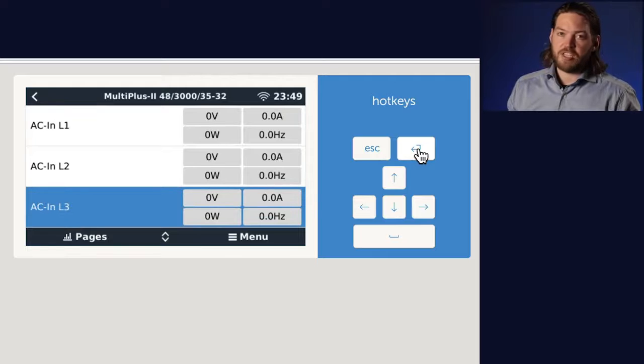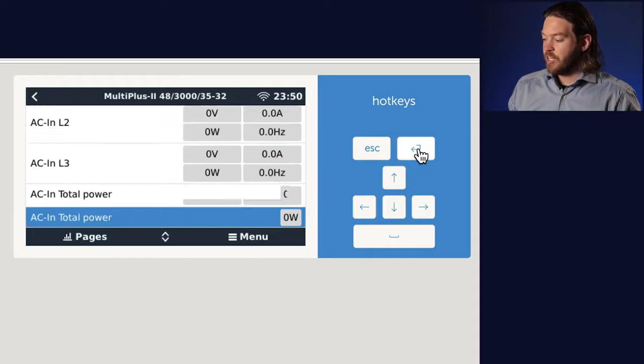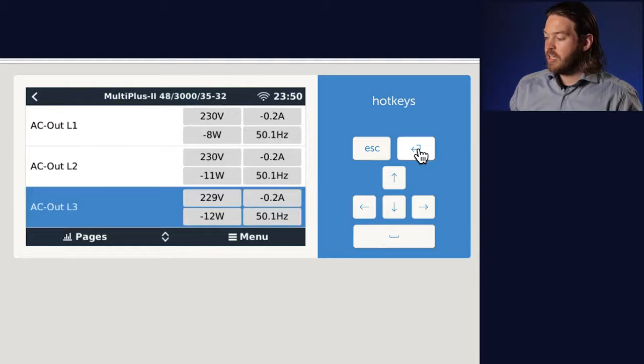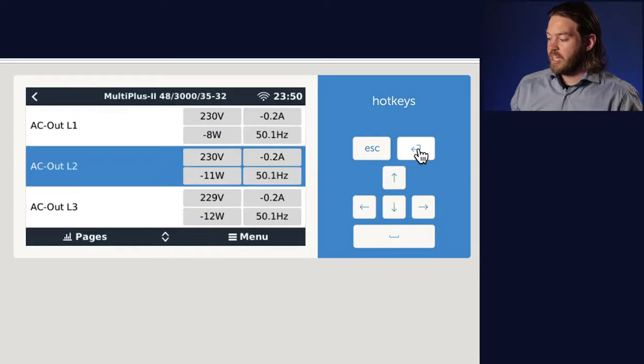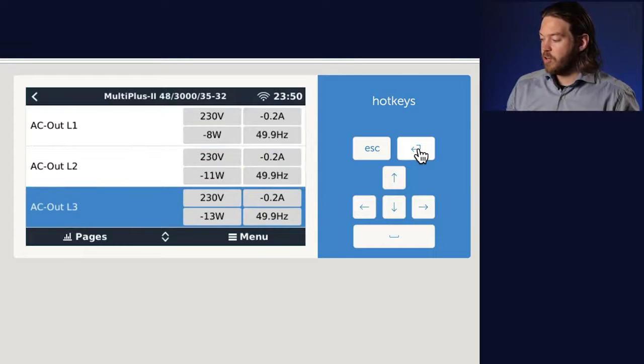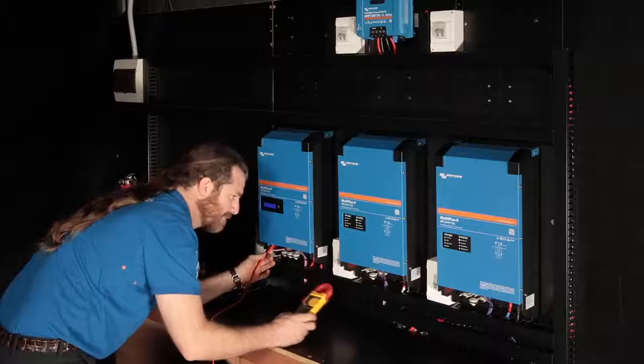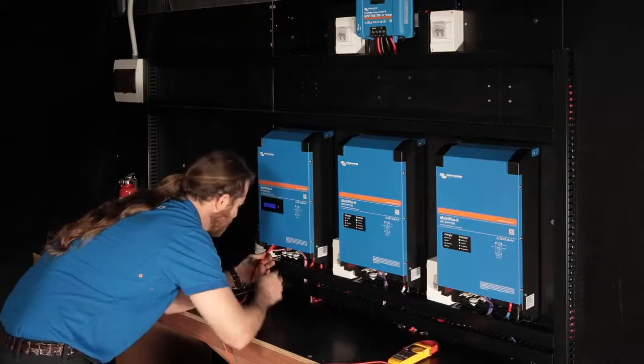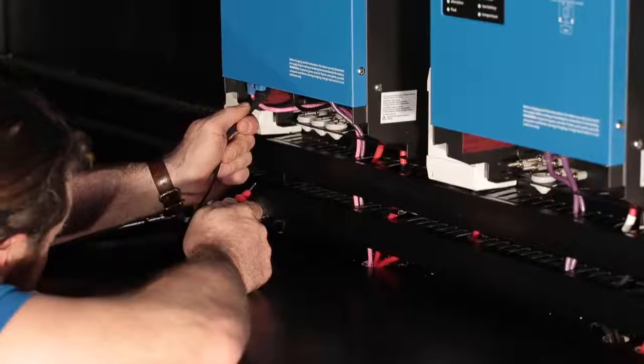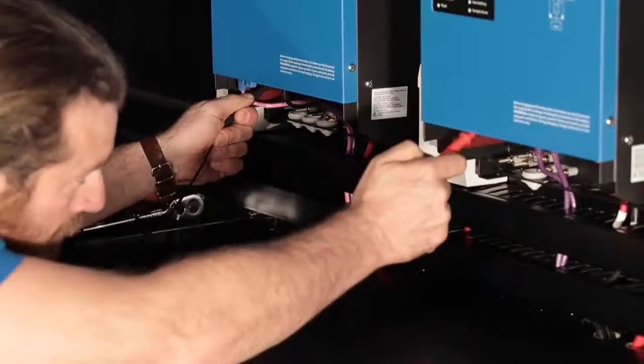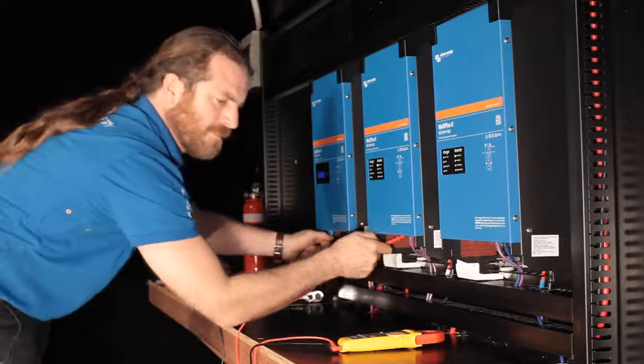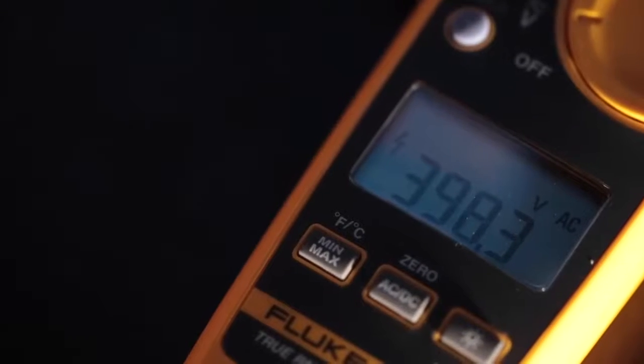Now there's no AC connected in to these systems at the moment, no AC in or AC out, but we can see there's 3 phases shown in the menu here, AC out L1, AC out L2 and AC out L3, and all is looking pretty good. You can further confirm this by using a multimeter to take a voltage reading between the 2 actives on the units. Now be careful doing this is going to give you 400 volts, so make sure your multimeter is appropriately rated and you're suitably qualified to be taking readings at those high voltages, because it can be quite dangerous.